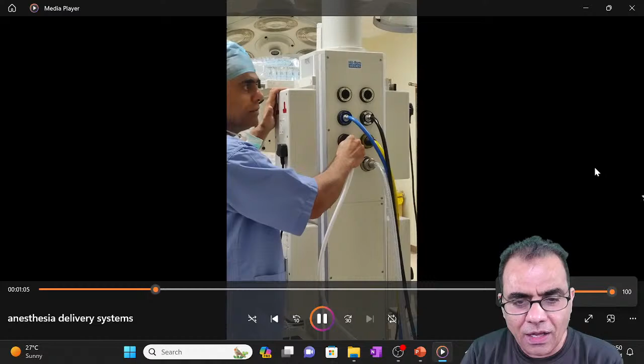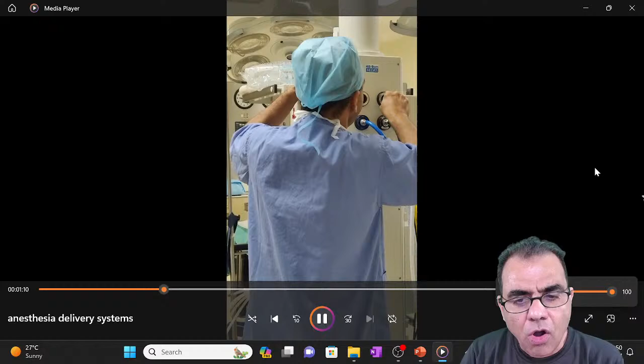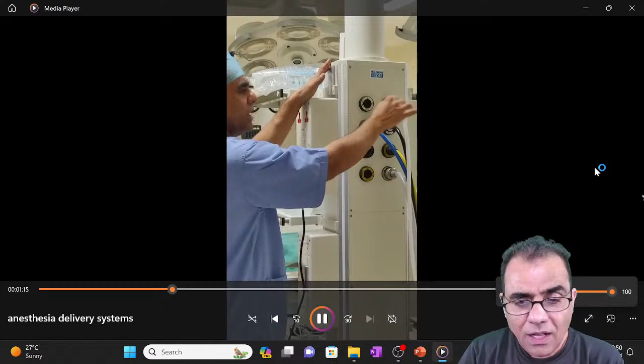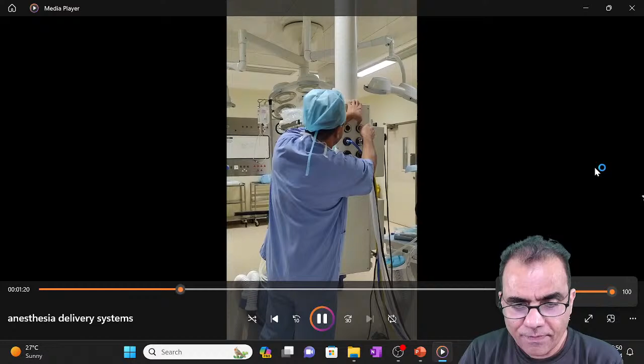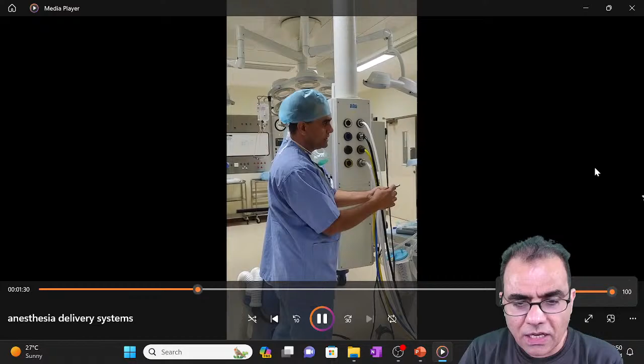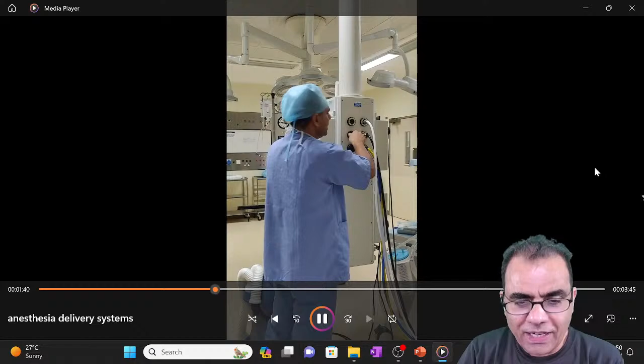So we'll see, this is an oxygen pipe, and this diameter I'll try to fit in this air slot. I'm not able to do it. I can only fit it in the oxygen slot. So this is the diameter indexed safety system. This is very important to prevent wrong fitting of the central supply pipelines. Similarly, you can see this diameter slot is there, so that cannot fit. See, if I try to fit nitrous oxide, it will not enter. So this is an important preventive measure.